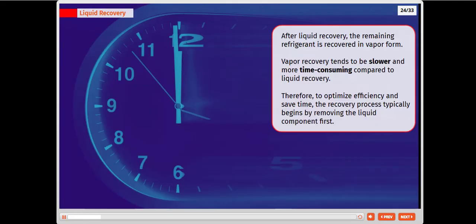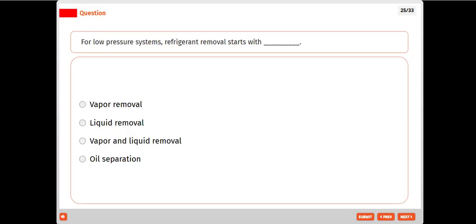After liquid recovery, the remaining refrigerant is recovered in vapor form. Vapor recovery tends to be slower and more time-consuming compared to liquid recovery. Therefore, to optimize efficiency and save time, the recovery process typically begins by removing the liquid component first. For low pressure system, refrigerant removal started with liquid removal.